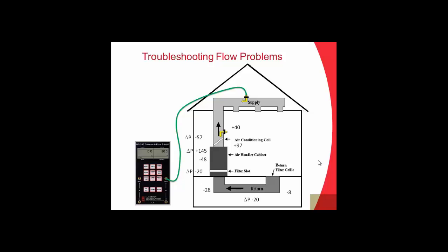Our next measurement we're taking up in the supply ductwork, and we're seeing 20 pascals at that location. So we're seeing 20 pascals, so we have 40 pascals down here. So we've got a difference. We've dropped 20 pascals across that spot in the ductwork. So now, if you took a measurement at one of these registers, you'd see that 20 pascal drop from going from the ductwork down to this register. So you can see that all of these pressures are additive, and they'll be highest at the pressure right across the fan.